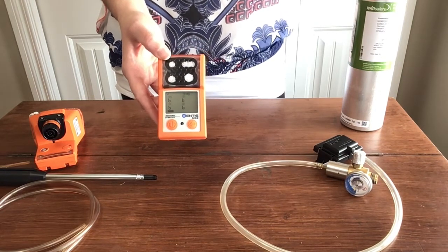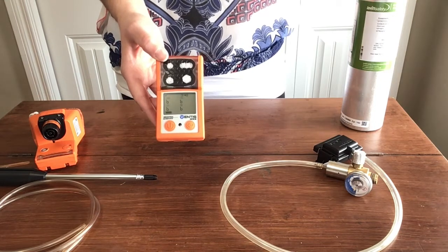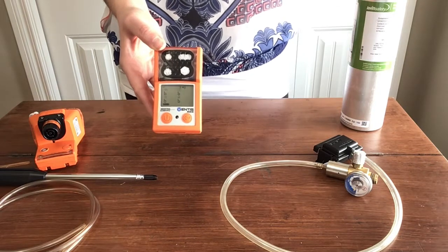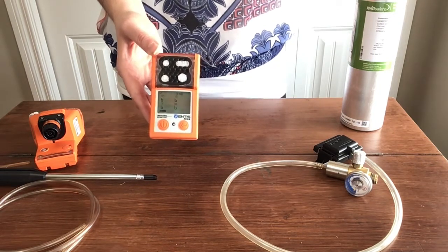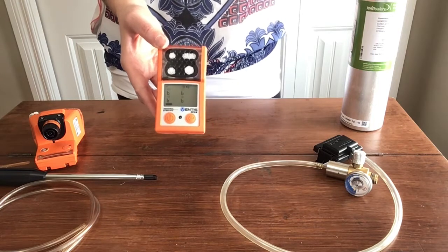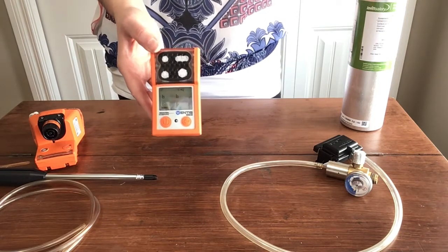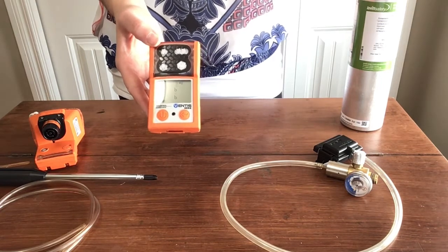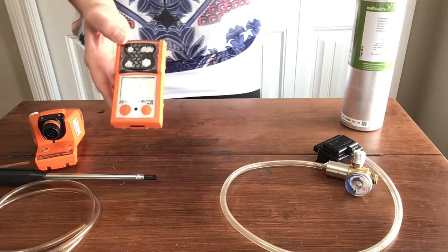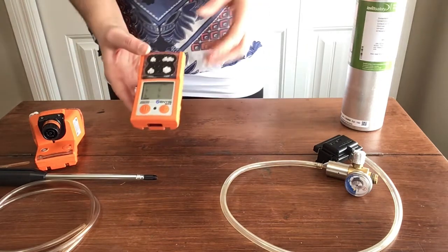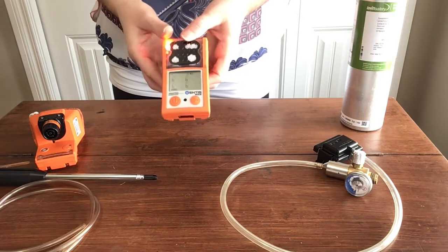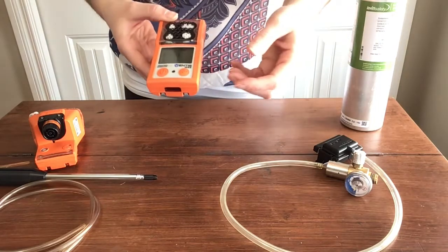Okay. In addition to that, the third thing, we have to do a fresh air zero. The reason we do a fresh air zero is to essentially set a baseline of fresh air for the unit and for the sensors so that it knows when it's going outside of that norm. Okay. This unit, unlike a lot of our other equipment, does not require a leak test. It does not require a post-use calibration. So we'll get to the monthly calibration first. In order to get to the monthly calibration screen, you have to go through the fresh air zero screen, okay? And actually, just give me a moment, I'll do that in a second after we get this set up.